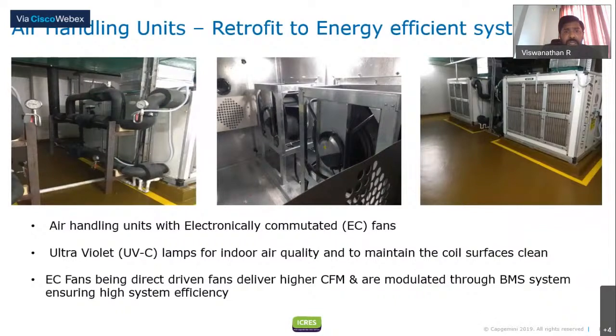And these are energy efficient air conditioning equipment. We have installed the latest technology of EC fans. These are electronically commutated fans, which are direct driven, and they consume 30% less energy than a conventional fan. Being direct driven, they deliver higher performance than a centrifugal belt driven fan. So here we get both advantages: we get more CFM for lesser power. Unlike a conventional centrifugal fan, which requires a VFD, variable frequency drive, to modulate the fan, these fans have an inbuilt inverter. So we can control them automatically, and these fans also get modulated based on the return air temperature.